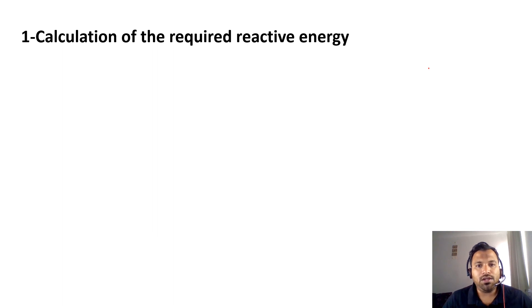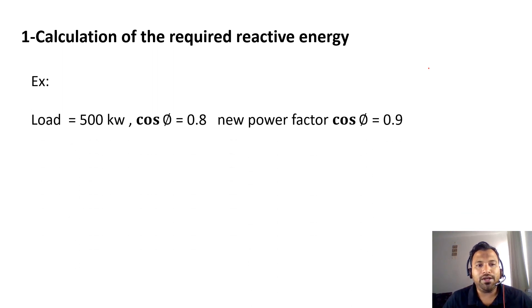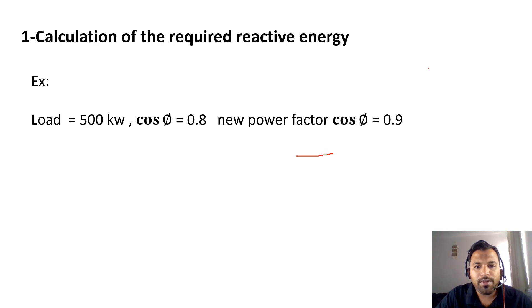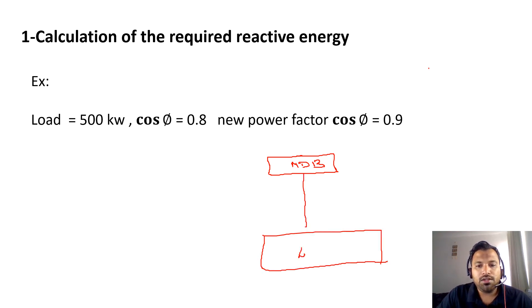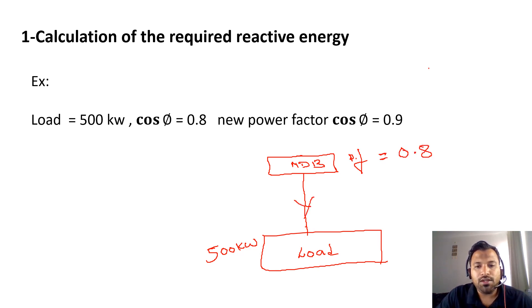Step 1 is finding out the reactive energy. Here's an example: I have a total load of 500 kilowatts and a power factor of 0.8, and I want to improve the power factor to 0.9. Consider this is your main distribution board — from the main distribution board, this is your load of 500 kilowatts. In the main DB, you have a power factor meter, and when power is applied, it shows a power factor of 0.8.